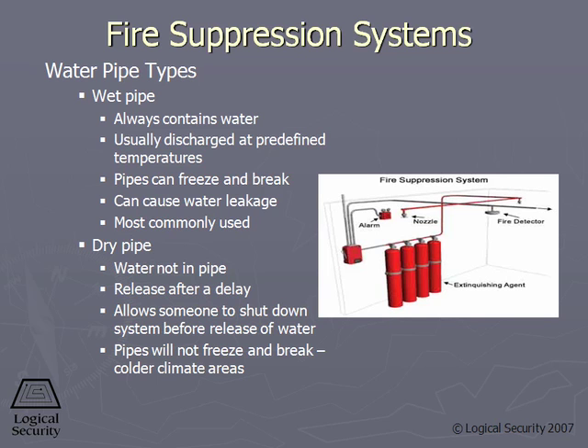The second type of sprinkler system you need to understand is called the dry pipe. The dry pipe has the same sprinkler system being distributed throughout the facility. However, the water doesn't fill the pipe. The water is actually contained by a shutoff valve that is away from the sprinkler head itself.